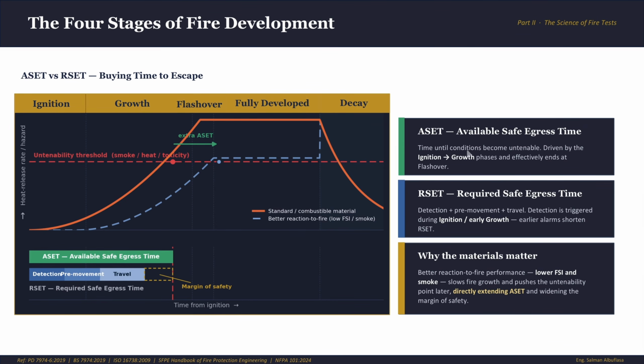And now we have two clocks, the ASET and the RSET. The ASET is the available safe egress time. That's the time you have. It's how long until conditions in that space become untenable, until the smoke, the heat, and the toxic gas cross the line where a person can no longer survive or escape. You can see the line at the top, the untenable threshold. It's right around here, where these two lines cross.